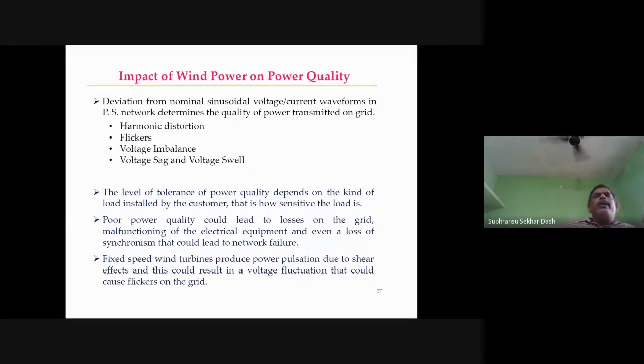Now with poor power quality, suppose a flicker is there, what happens? There is a chance that your equipment may get damaged. So indirectly there will be losses to the grid, because if power fluctuation is there, most of the equipment may burn or get damaged. Malfunctioning of the equipment and even a loss of synchronization could lead to network failures. Fixed speed wind turbines produce power pulsation due to the shear effect, and this could result in voltage fluctuations that could cause flickers on the grid.